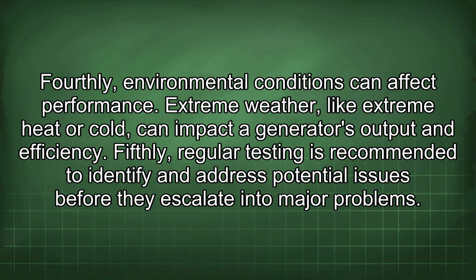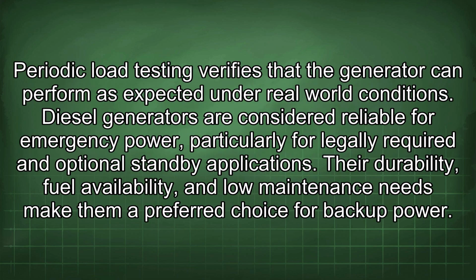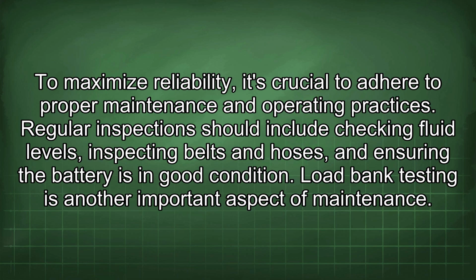Fifthly, regular testing is recommended to identify and address potential issues before they escalate into major problems. Periodic load testing verifies that the generator can perform as expected under real-world conditions. Diesel generators are considered reliable for emergency power, particularly for legally required and optional standby applications. Their durability, fuel availability, and low maintenance needs make them a preferred choice for backup power. To maximize reliability, it's crucial to adhere to proper maintenance and operating practices.